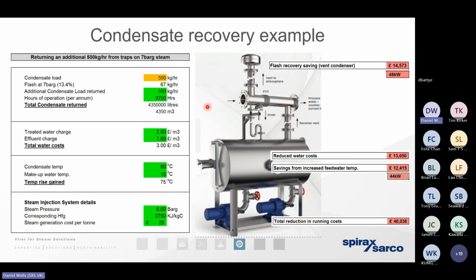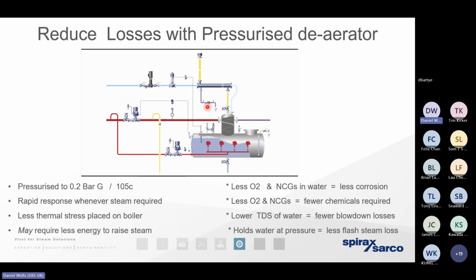Not going to go through this too much. Suffice to say that if we've calculated the cost of steam, and we know that there's 25% of the total heat energy in the steam that is retained within the condensate, the steam tables tell us that, then we can apply the same calculation. 25% of the cost of steam is retained in the condensate. So if we calculated our steam at £100 per tonne, that is the value of the condensate. So we can calculate the payback in installing the appropriate condensate return system and ensuring that we get as much of that hot water back to the point of use as we can.